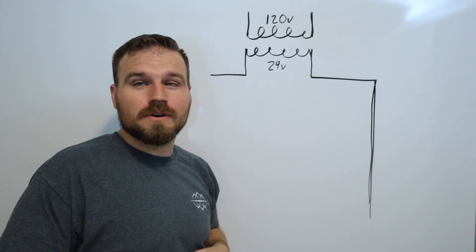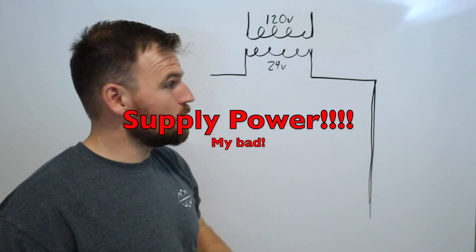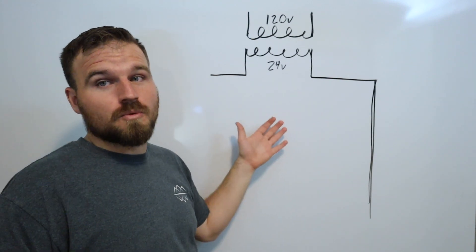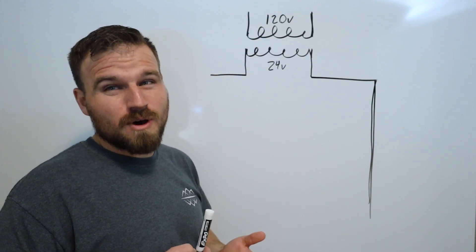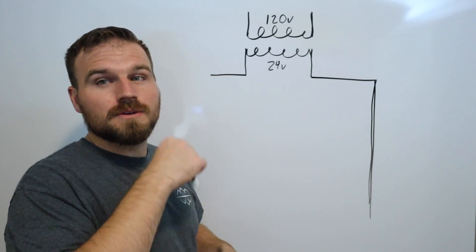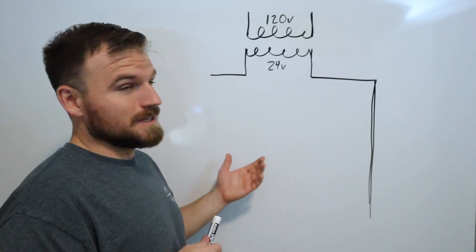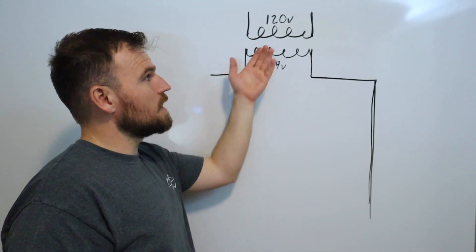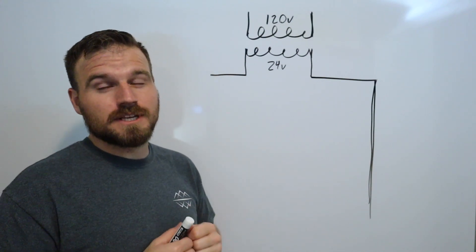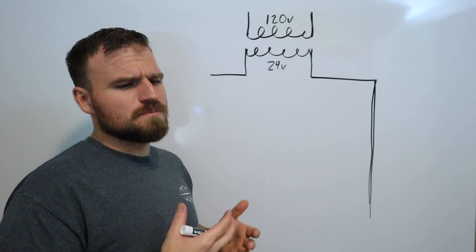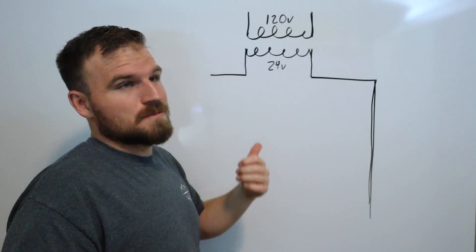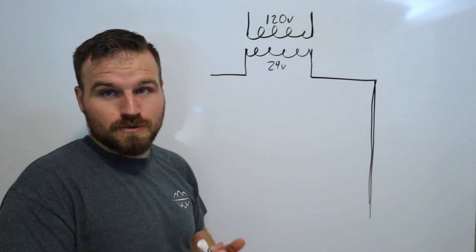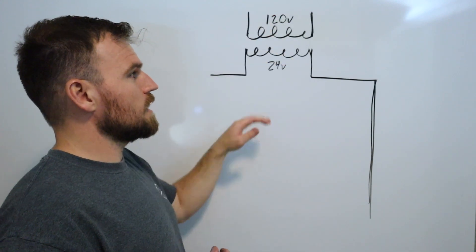I drew the transformer up top. The power coming into the transformer is called incoming power, while the power on the other side is called control power. For this circuit, our control power is 24 volts AC. It is also possible to run the whole control power off 120 volts - that's very common in simpler setups where everything runs at 120 volts, eliminating the need for a transformer altogether.